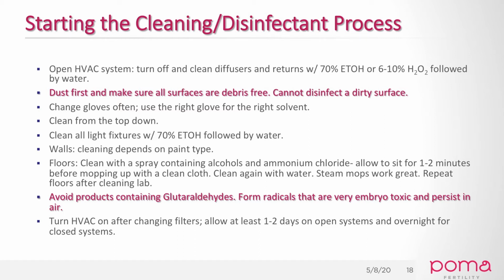So now that you've cleaned the lab and you're standing there, the next thing I would do is look around at your equipment and ask, okay, what's the highest potential? What's my lowest potential? Water baths, box incubators, circulating water baths, incubator fans, all of these things are areas that have high potential, and these should be cleaned as I've listed here in the slide, because these are great sources of bacterial and fungal contamination. So, this is time to do that.